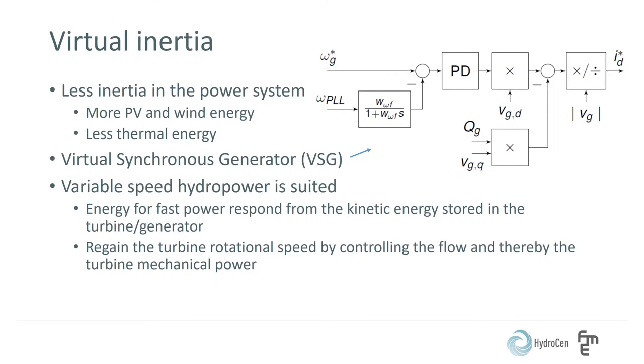Variable speed hydropower is well suited for delivering virtual inertia, since it can obtain the energy from the kinetic energy stored in the turbine and generator to change the output power almost instantaneously by converter technology. Next, the turbine rotational speed can be regained by controlling the turbine flow and thereby the turbine mechanical power. Thus, the variable speed hydropower plant can operate at a new stationary output power after the disturbance.